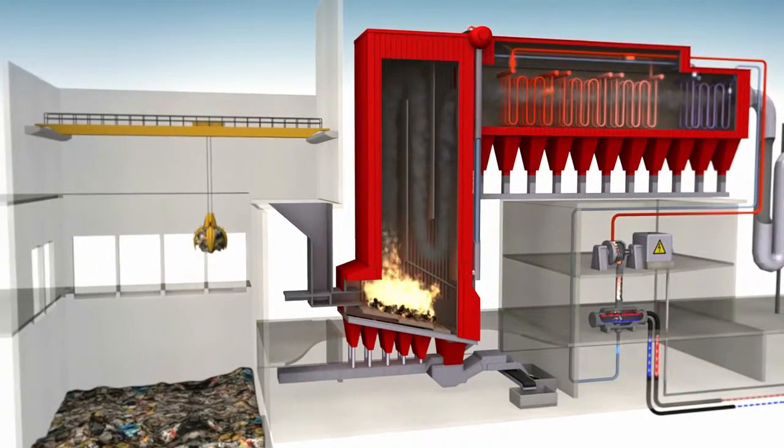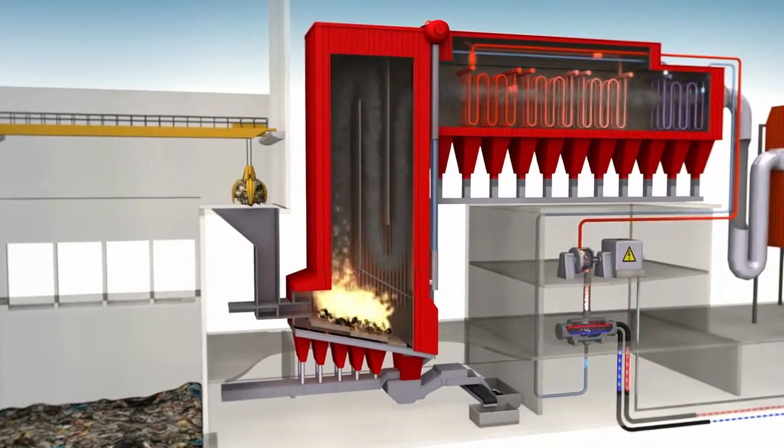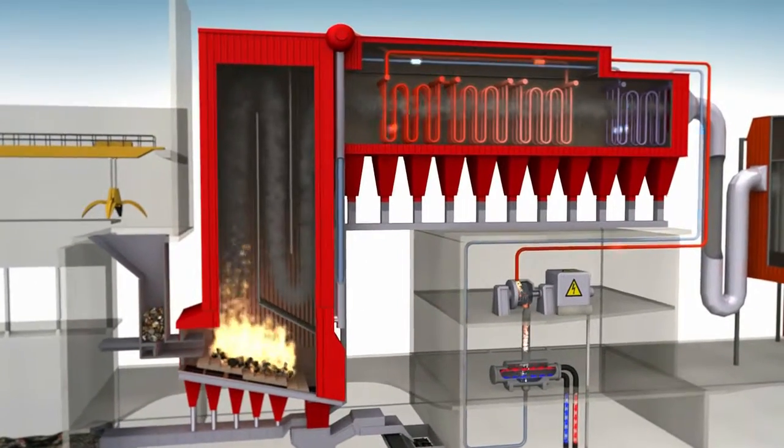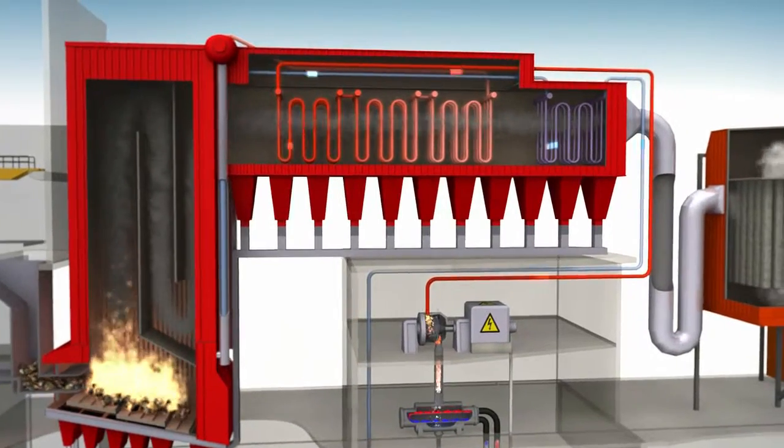Inside the boiler, there are almost 100 kilometers of water pipes. Water is heated to 270 degrees Celsius, which is the boiling point at a pressure of 50 bar. The steam created is then superheated to a temperature of 425 degrees Celsius.